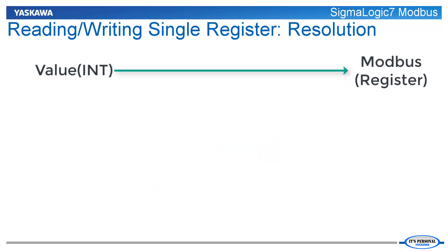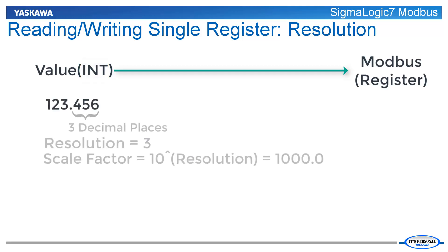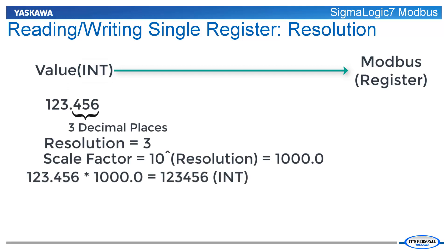Setting the resolution is an example of writing a value to a single 16-bit register. For the Sigma Logic 7 Modbus, recall that all values are sent as integer data. In order to send floating point data, values are scaled up by a number of implied decimal places to an integer. The resolution register is used to specify the number of implied decimal places. Since the resolution setting has a limited range, the value easily fits into one 16-bit register.